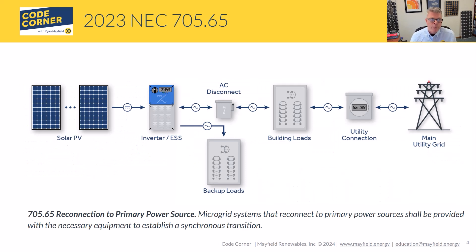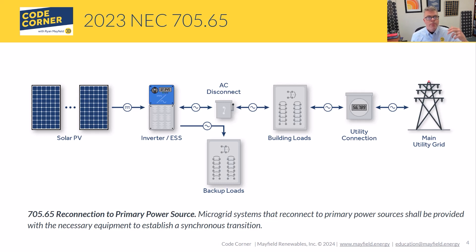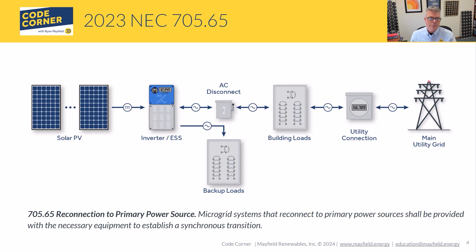Section 705.65 covers reconnection to a primary power source. Microgrid systems that reconnect to a primary power system shall be provided with the necessary equipment to provide a synchronous transition — these are our microgrid interconnect devices, which we'll cover in the next video. In a small home or residential application, where you have the grid coming into your main panel and a solar plus storage system feeding backup loads, that connection and reconnection happens within the inverter ESS system.